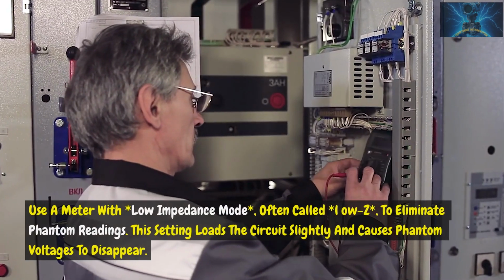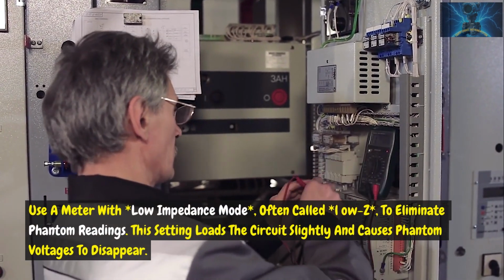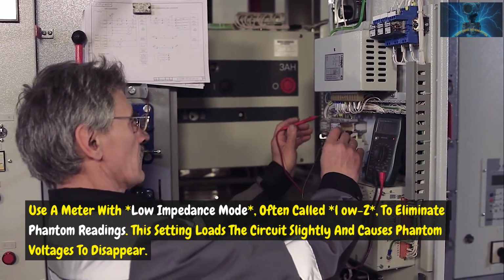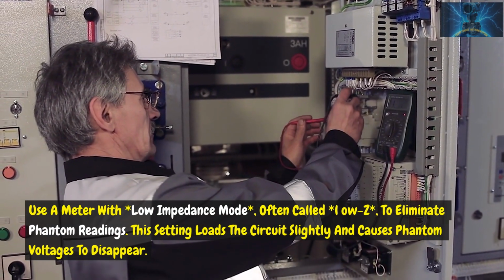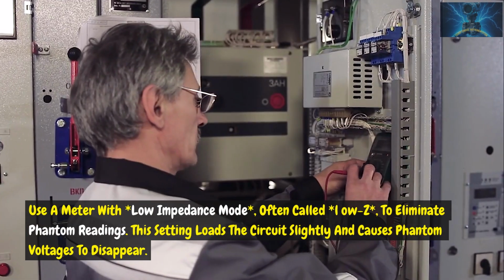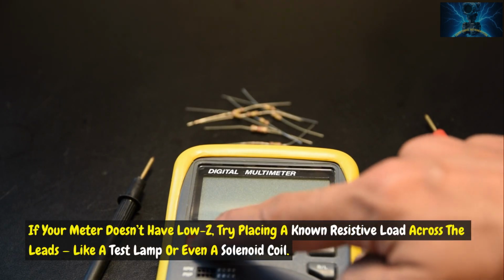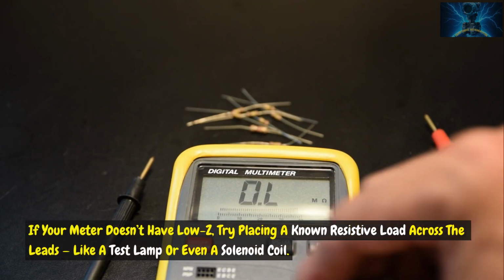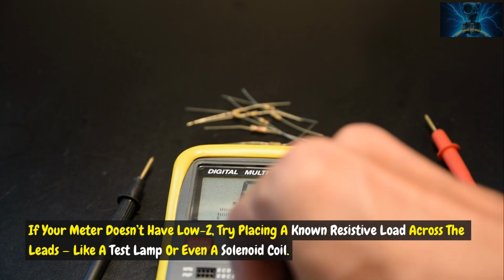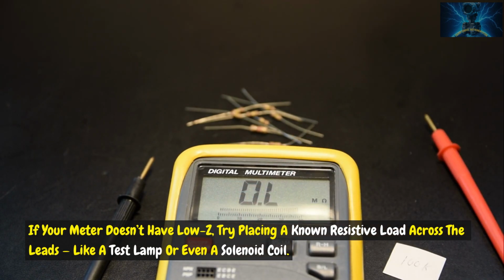Use a meter with low impedance mode, often called low Z, to eliminate phantom readings. This setting loads the circuit slightly and causes phantom voltages to disappear. If your meter doesn't have low Z, try placing a known resistive load across the leads, like a test lamp or even a solenoid coil.